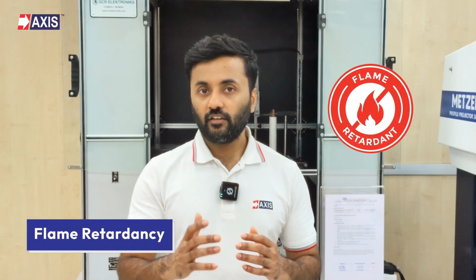Also, we need to check if flame retardancy is required. In areas with high electrical load, the material must resist the spread of flames. If it can't, it will support combustion and allow fire to spread along the cable. So, you must select the material based on the actual chemical and fire exposure at site because polyolefin, PVC, fluoropolymers, silicone, and Viton all behave differently under chemical stress and flame conditions.